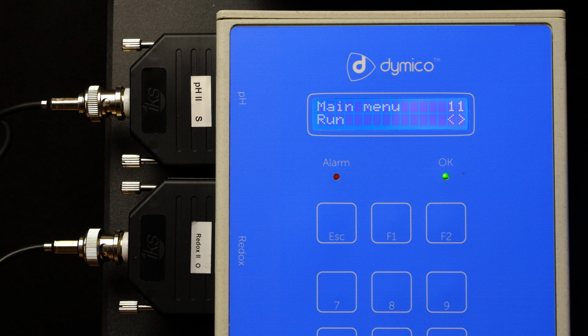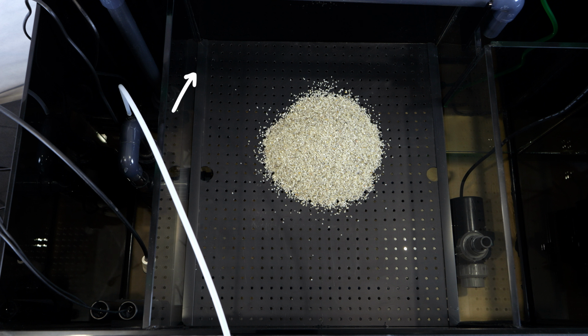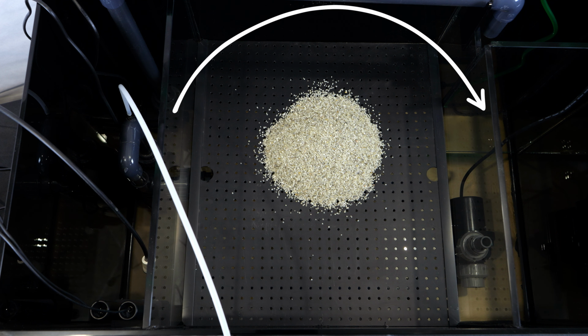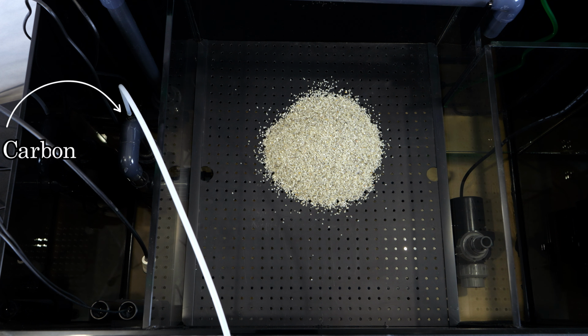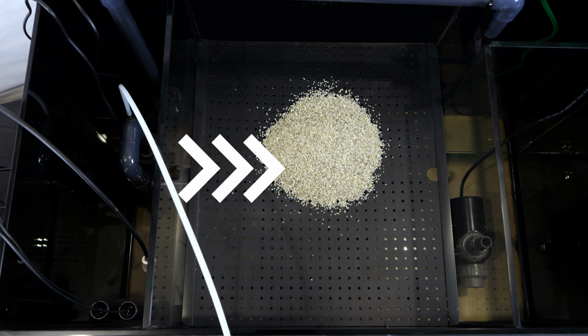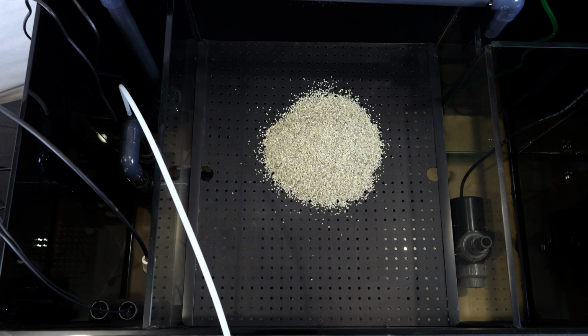You must see the following steps in this exact order. During 30 seconds, nothing. DyMiCo is measuring the redox. The small return pump is on for 30 seconds to 15 minutes. The carbon dosing pump is on for a couple seconds. The process pump is on. You will see a water level change in the left compartment compared to the middle compartment.